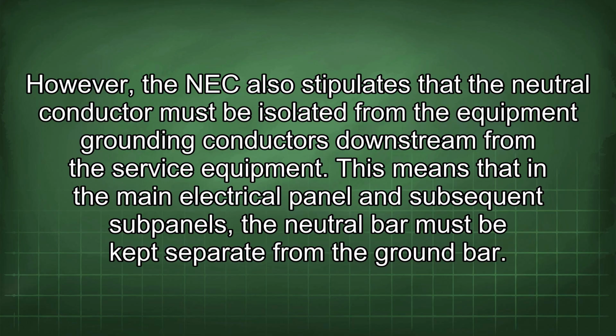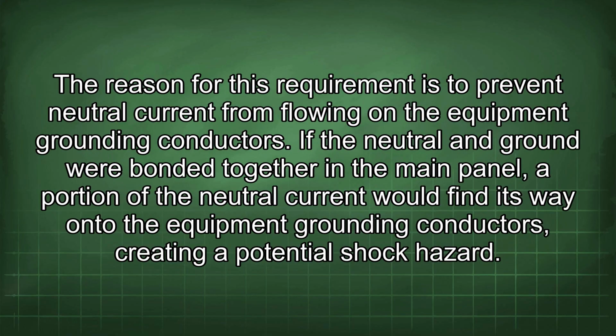However, the NEC also stipulates that the neutral conductor must be isolated from the equipment grounding conductors downstream from the service equipment. This means that in the main electrical panel and subsequent subpanels, the neutral bar must be kept separate from the ground bar. The reason for this requirement is to prevent neutral current from flowing on the equipment grounding conductors. If the neutral and ground were bonded together in the main panel, a portion of the neutral current would find its way onto the equipment grounding conductors, creating a potential shock hazard.